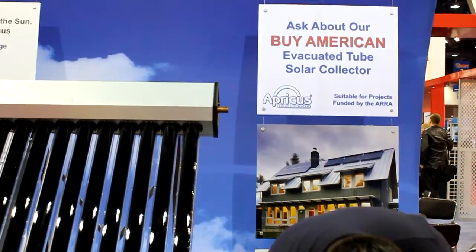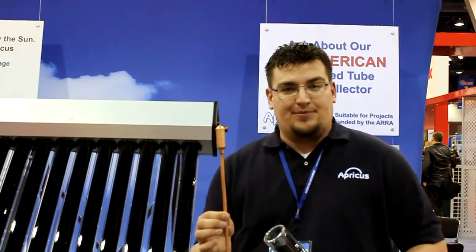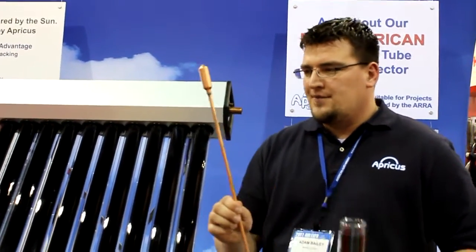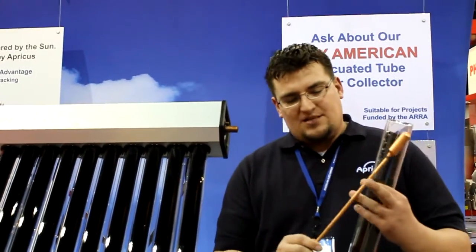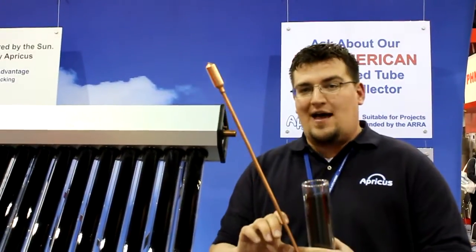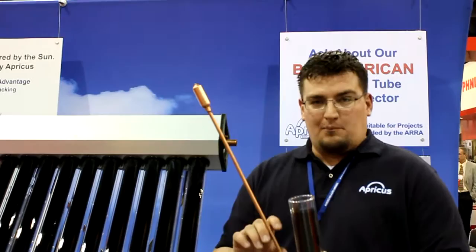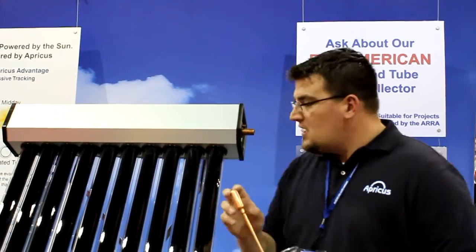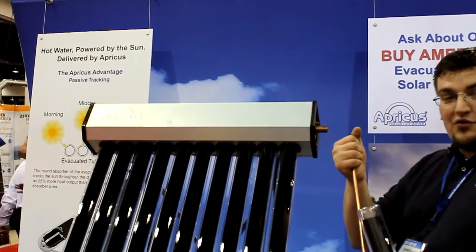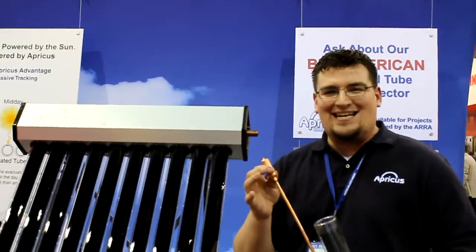What we've done is combined the evacuated tube with a heat pipe. Now a heat pipe is phenomenal technology — it's a micro steam generator. Inside of this tube is about a tablespoon of water. Because it's pulled under vacuum, it boils at about 85 degrees Fahrenheit. As soon as that water boils, it turns to steam and comes up here to this bulb. As the water flows through this collector, it pulls the energy out of the steam, condensing that steam back into water. So effectively we're taking advantage of the latent heat of steam.